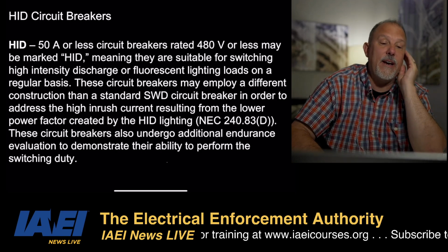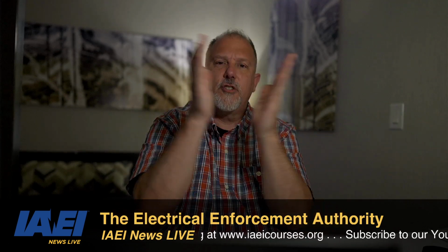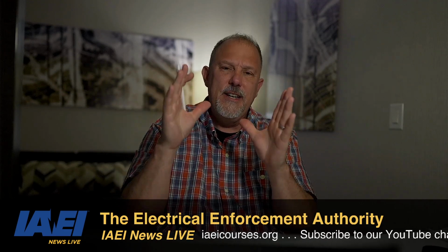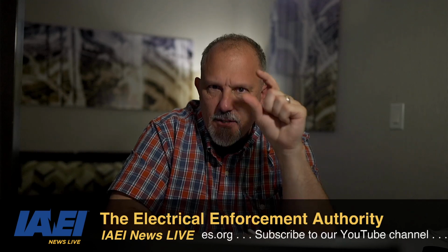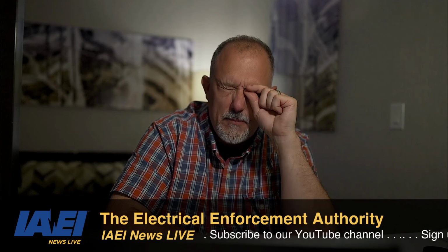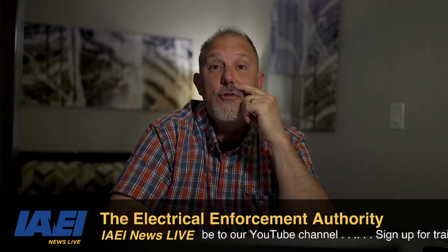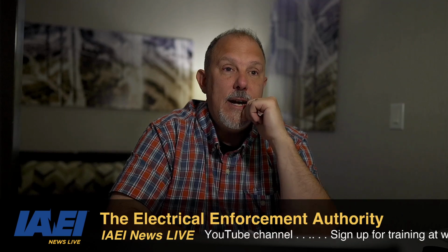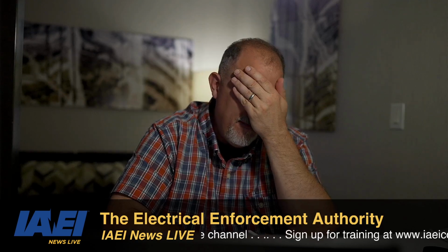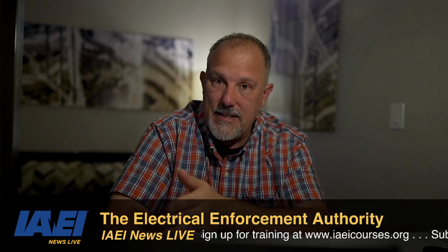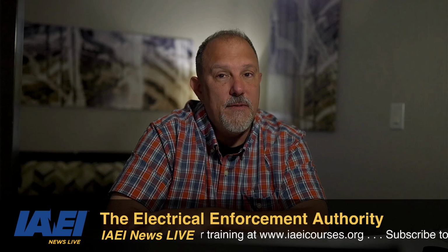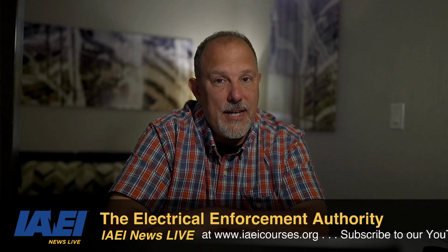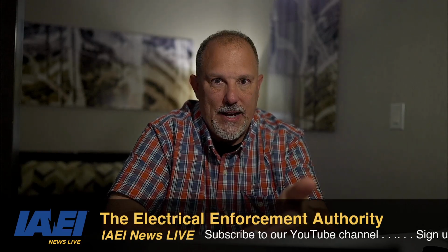Remember, think about a circuit breaker. What's a circuit breaker doing? A circuit breaker is going to be opening and closing contacts, and it's going to be drawing an arc between those contacts. The characteristic of that arc is going to depend upon the power factor of the circuit that you're trying to open and close on. Now, power factor. It will vary. If I'm dealing with a specific type of light, like fluorescent or HID, they'll know the type of load that we're dealing with, and that gives you an indication of what that power factor is going to be, so we can test under those inrush currents at those power factors.